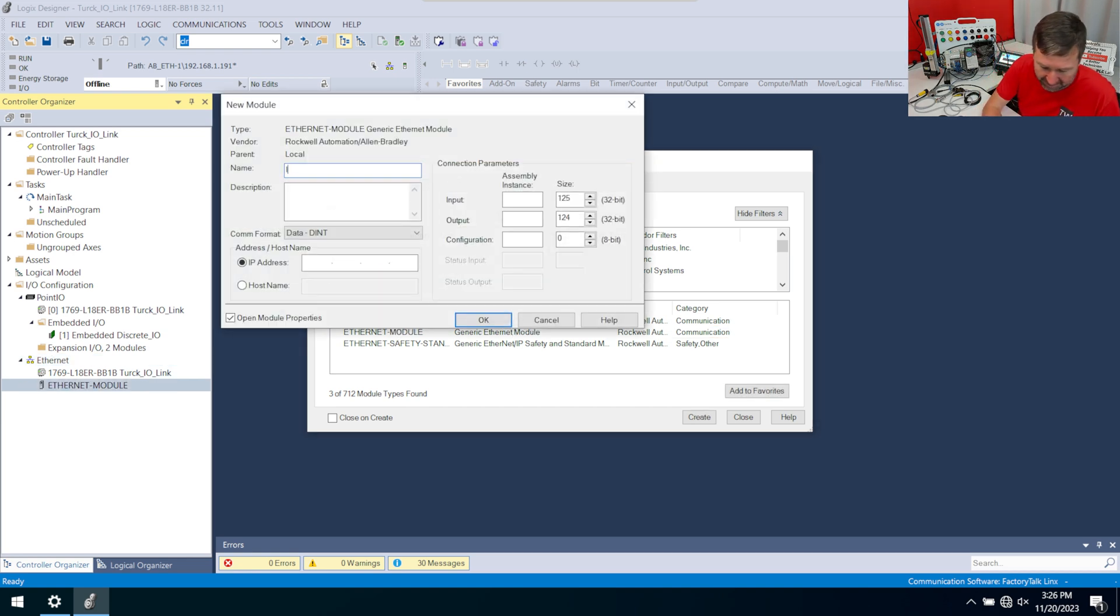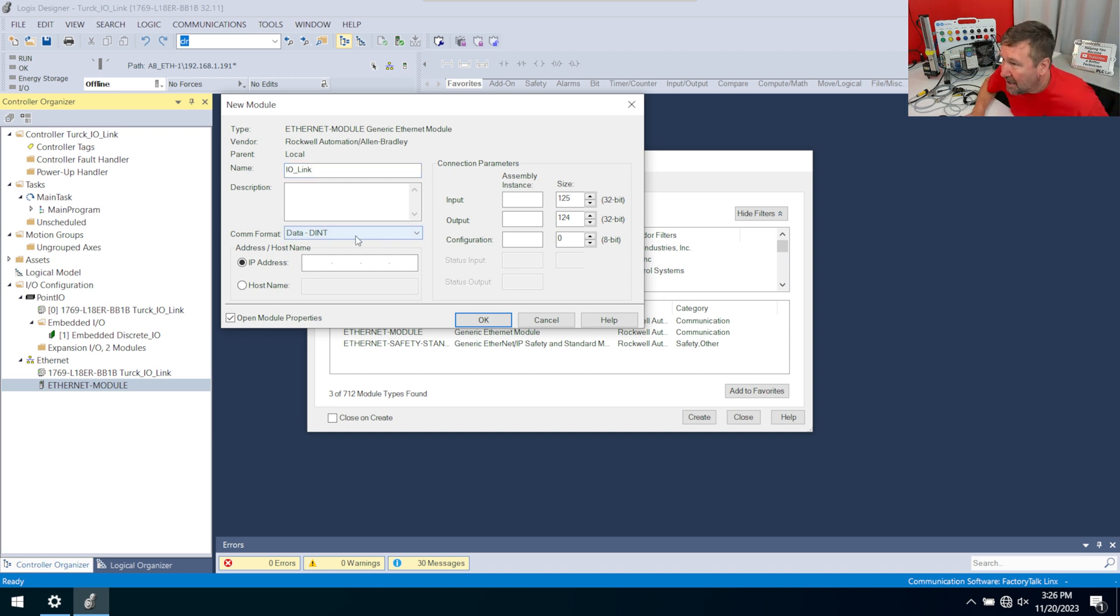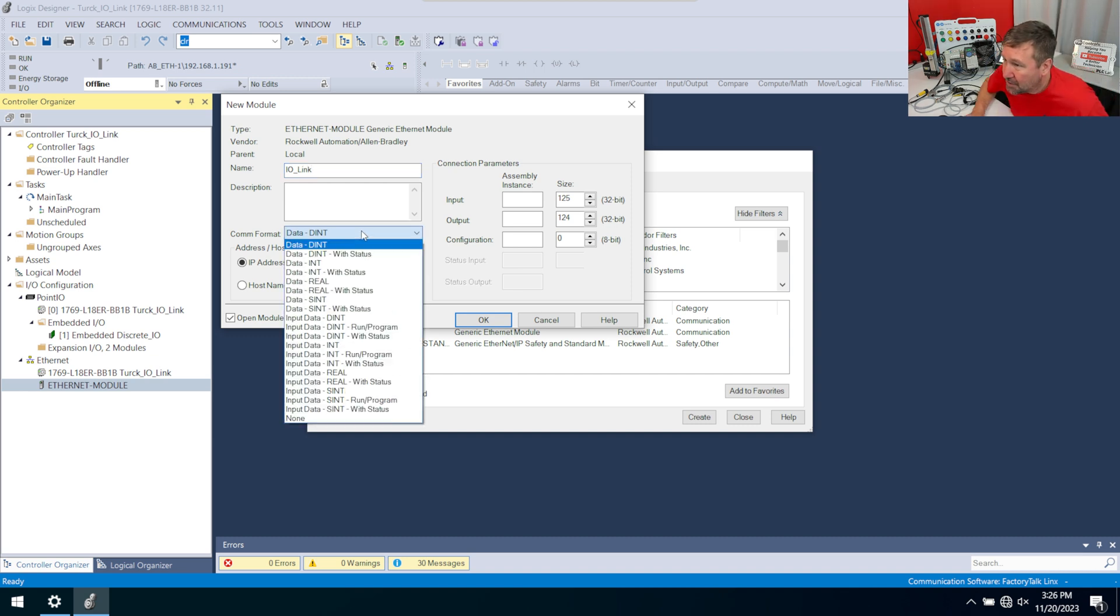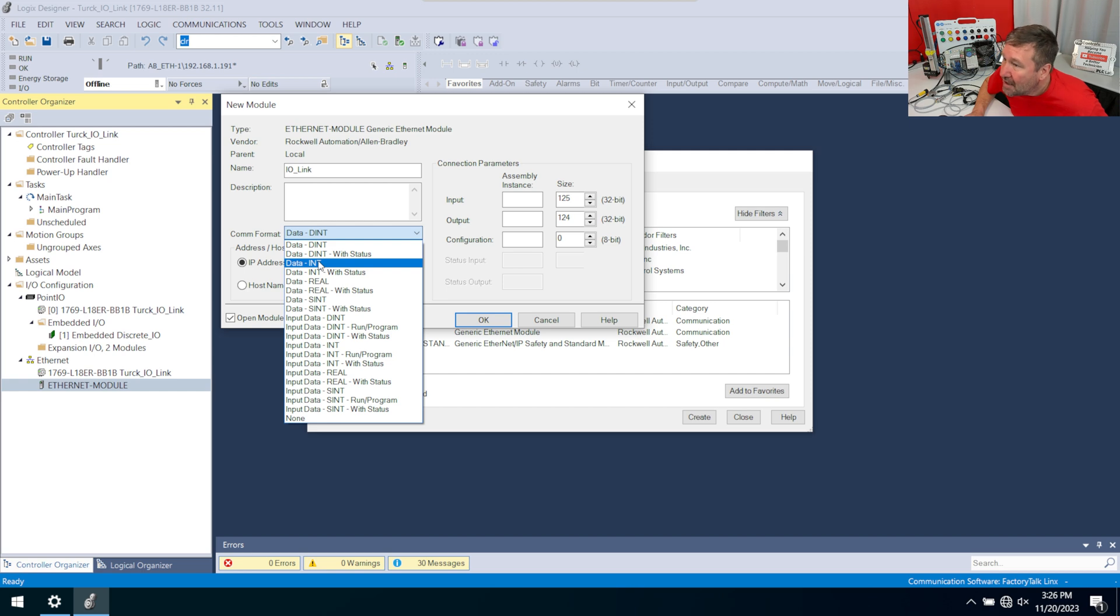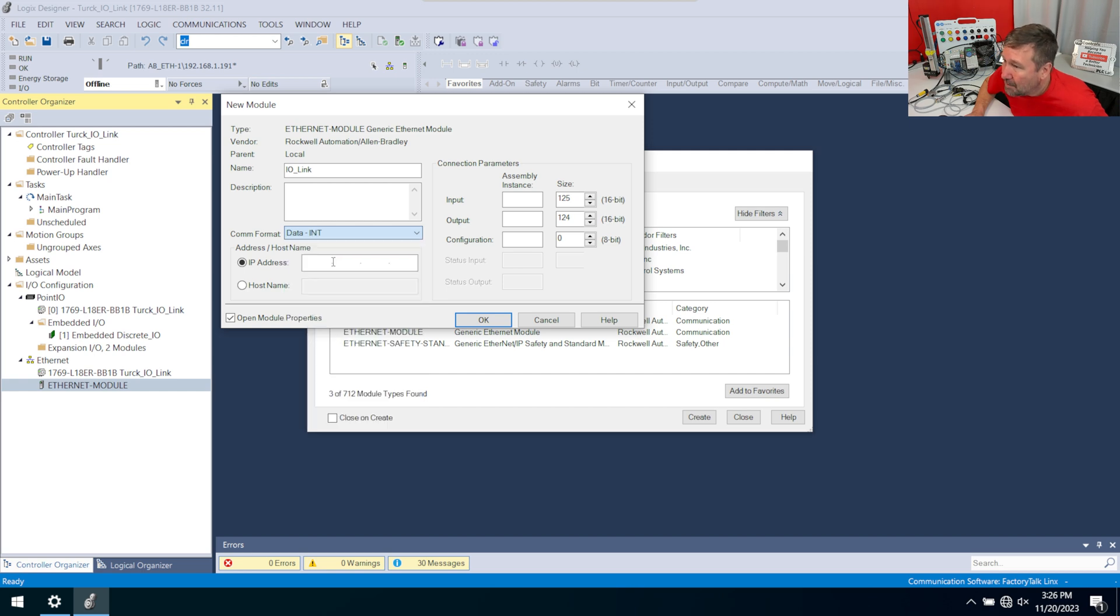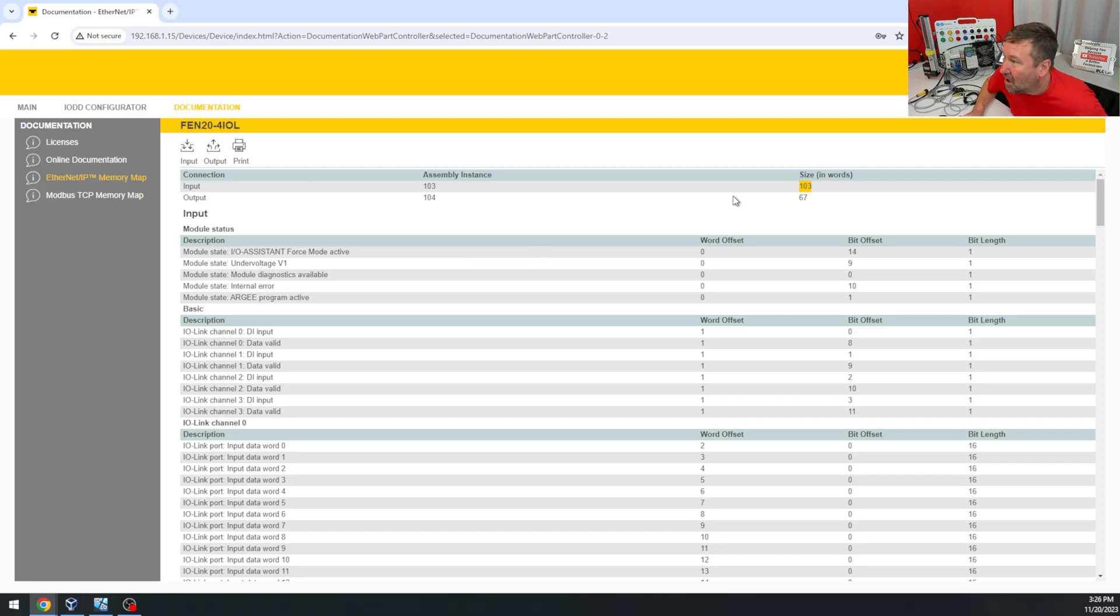I'm going to call this my IO-Link. And then for our communications format, and this trips me up often, you got to get this one right the first time. It's the only thing in Studio 5000's generic module they won't let you change afterwards. Our data type is going to be INT, mainly because all of this is based on words or 16-bit numbers.